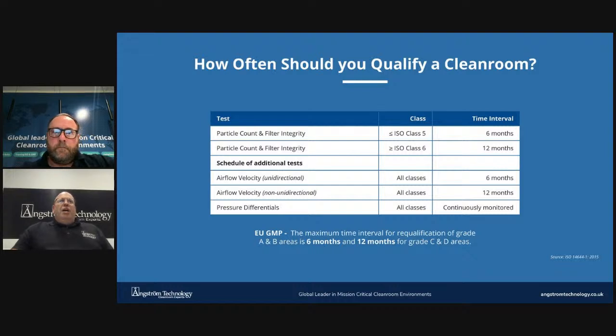ISO 14644 Part 2 of 2015, which is monitoring to provide evidence of cleanroom performance related to air cleanliness by particle concentration, recommends customers to complete risk assessments and monitoring plans to determine the frequency of testing and validation for their individual processes. It states that the suggested maximum time interval between airborne particle counting of a cleanroom of ISO class 5 and below is 6 months, and ISO class 6 and above is 12 months. However, this should be assessed to ensure it is in line with your own monitoring plan and risk assessment, which is required to be reviewed on a regular basis.